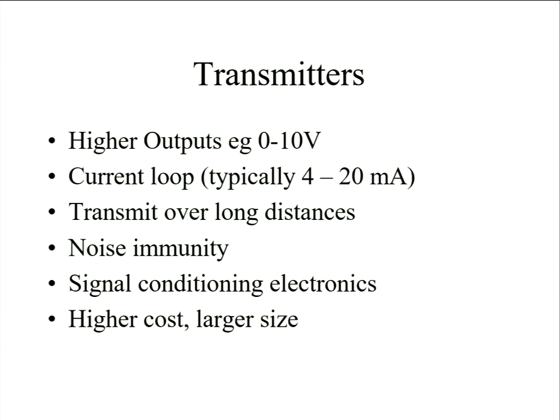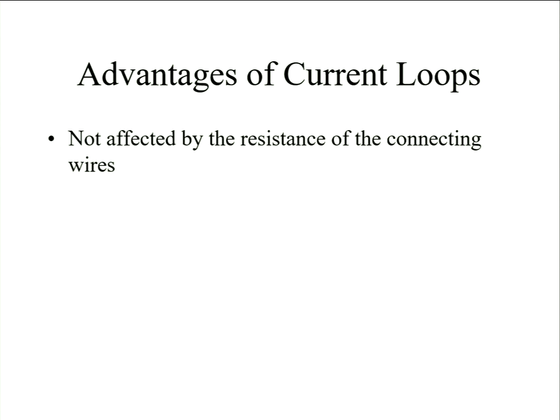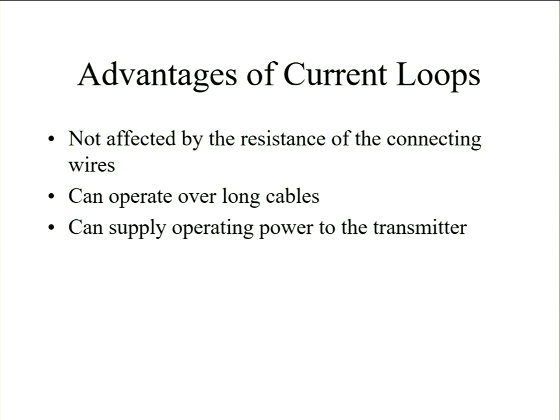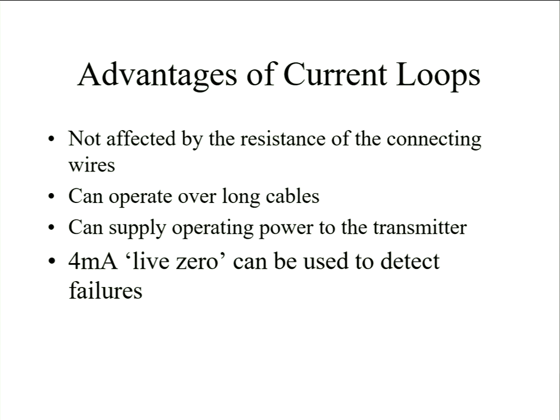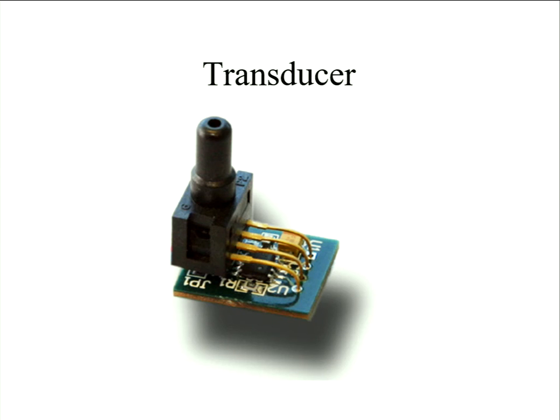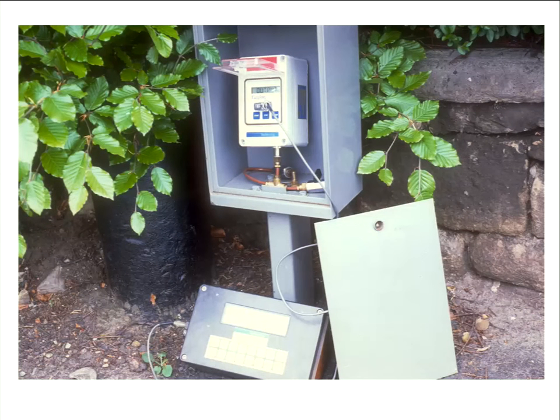Whereas transmitters can be bigger devices. Typically a lot of them work on this sort of strain gauge principle, so you're applying pressure, either a differential pressure or one side might be open to atmosphere. It flexes the diaphragm, and you measure that change through a strain gauge, which then gives you an electrical signal which you can convert into a pressure reading. There are capacitance based devices as well, but a similar principle. You're creating a change which will change the capacitance, which you can then measure, and there's a defined relationship of changing capacitance for that device. There's a change in pressure.